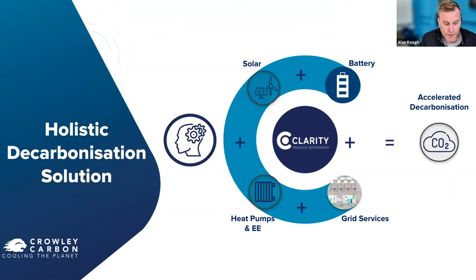That said, if you have a fuel bill for your gas boiler currently at 1 million, and you replace that with an electric boiler tomorrow, you'd have a 4 million bill, which most people aren't willing to pay. And just to say, the electric boiler could play a part in a particular site's configuration - it could be coupled with, say, just one stage of heat pump plus the electric boiler, and actually that can be an optimal commercial, technical and decarbonisation solution. So it would be very site-specific in terms of the ideal configuration or transition for particular consumptions and temperature/pressure requirements.